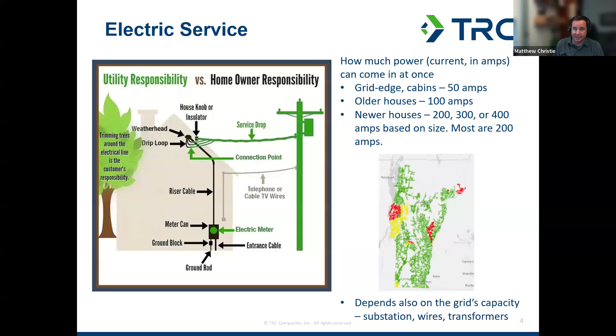The next thing in your house is your electric panel. That's the other place the energy flows, after it goes through your meter it goes to your panel, and it all goes through a main breaker. That's this little black thing at the top here, rated 60 amps, 50, 100, or 200, hopefully matching your service drop, but not always, though in most cases it is. Then that's split up into lots of circuits, the plugs and appliances go out to specific circuits serving various parts of your home.